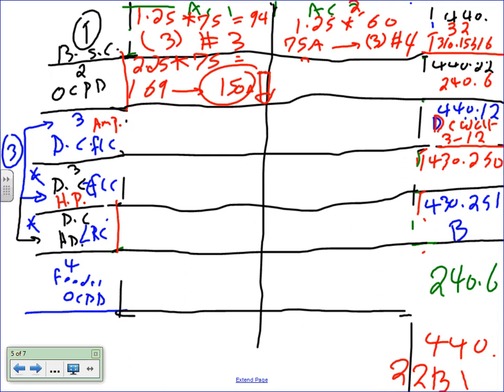This one is the same thing, 2.25 multiplied by 60. That will get you 135. You go down to 125 amp, done. Yes, sir. On the test, if you do it this way, but if you decided to be a smart aleck like Chad, and you put 1.75, Chad, I assume I'm going to use 1.75 from the code, and you size it, I will give you full credit too. So, you know what it says.